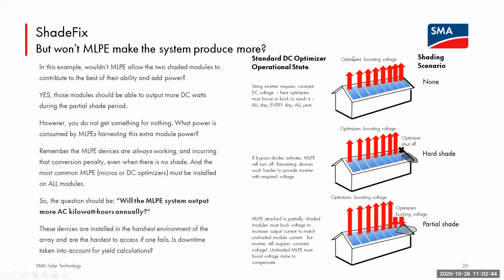So in a non-shaded situation, those traditional optimizers are still doing work behind each module. So they have the capability to buck and boost voltage that's coming into their optimizer units from the module, and they're cycling, right? So no matter what happens, they're getting warm, so they're generating heat. They're knocking you with an efficiency loss. And if there's no shade, they're still operating. They're still doing something up there. And that's every day, all year long. And that's a concern when you talk about long-term reliability.